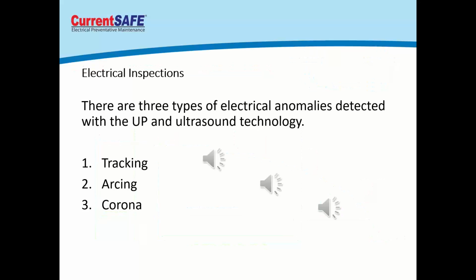I've got a couple of sound clips to play for you: tracking, corona, and arcing. Tracking and arcing are the two that happen on a low voltage distribution system, meaning below 1,000 volts. Corona only happens on medium and high voltage electrical distribution equipment — it takes that much voltage pressure in a system to create corona. So we typically hear tracking and arcing on the low voltage side, and in the medium voltage world we can add corona to that. In medium and high voltage, we can hear all three: arcing, tracking, and corona. I'm going to play this audio for you — this is what tracking sounds like.